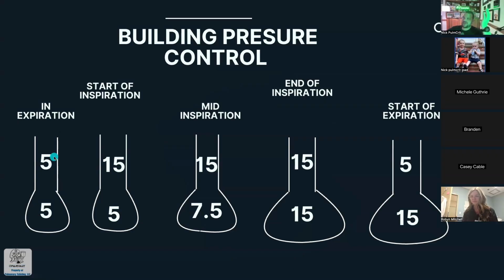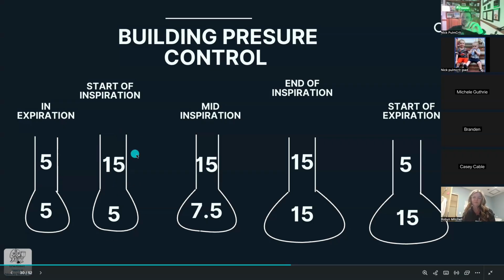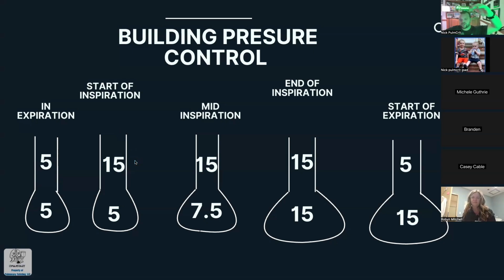Remember, in expiration, the pressure in the ventilator is the PEEP that we set, and we set it at 5. Now the ventilator kicks on, and now we're starting inspiration. So we set the airway pressure, the inspiratory pressure, if you will, to 15. So remember, our total pressure is 20, but our airway pressure, inspiratory pressure is 15. We had a PEEP at 5. The total is 20. So because we set up a delta pressure, we're going to start to get flow.